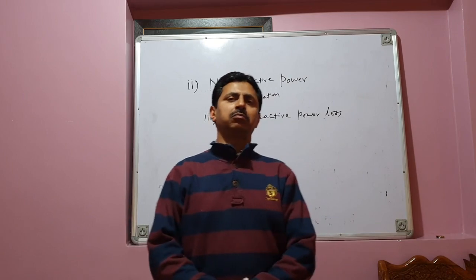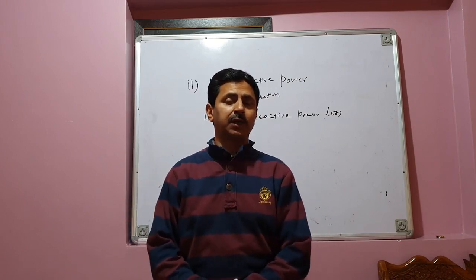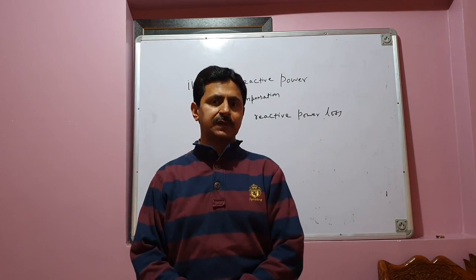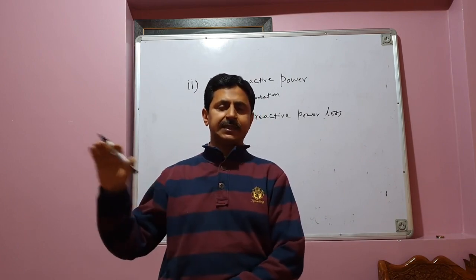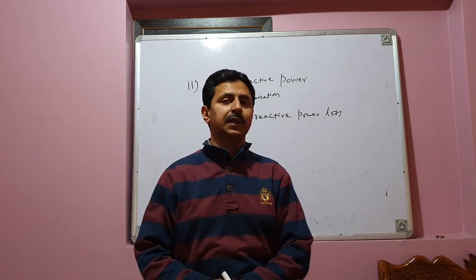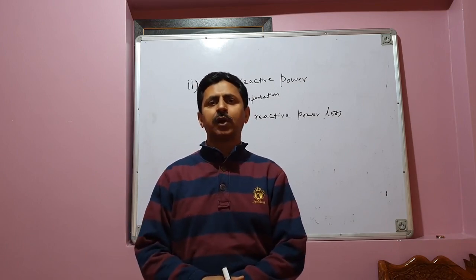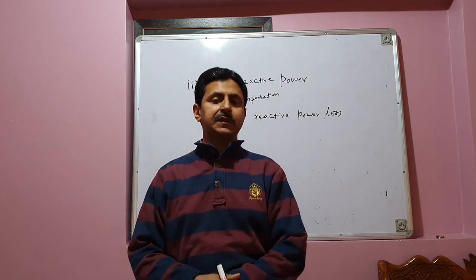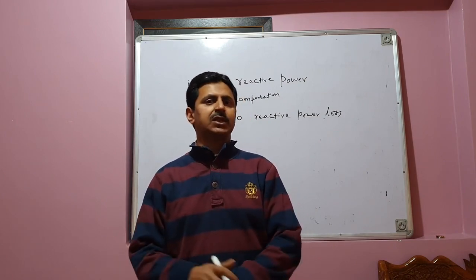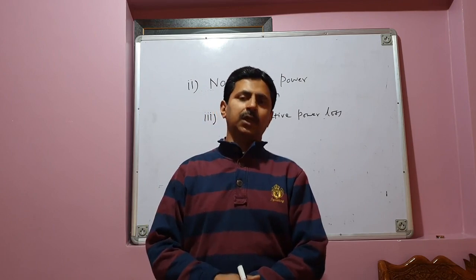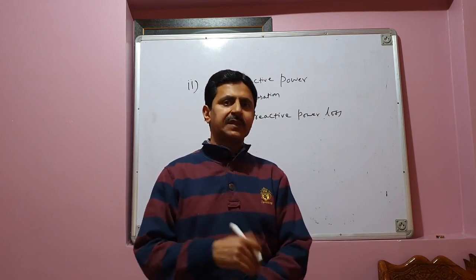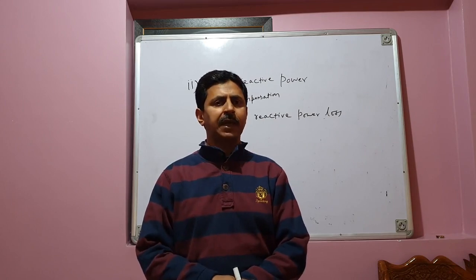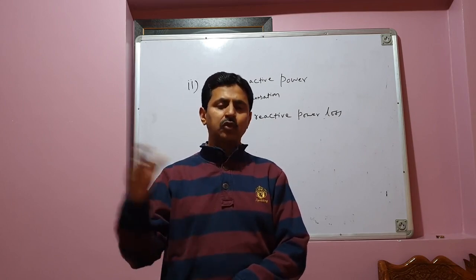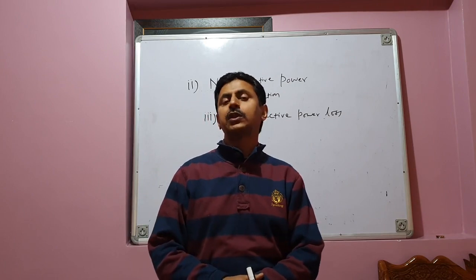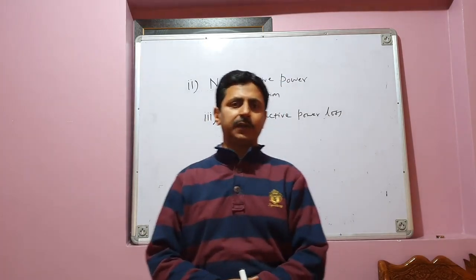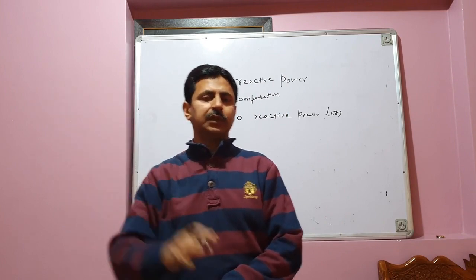I hope all of you know the difference between reactive power demanded by the load and reactive power loss. The reactive power which is flowing in the system is actually the reactive power which is demanded by the load, and most of the load which is connected to a power system is a reactive type of load. It may be induction motors, large induction motors in industries, or it may be domestic type load, commercial type load, or agricultural type of load. Almost all of this load is reactive in nature. So therefore this load demands the reactive power. This reactive power has to flow over the transmission line.